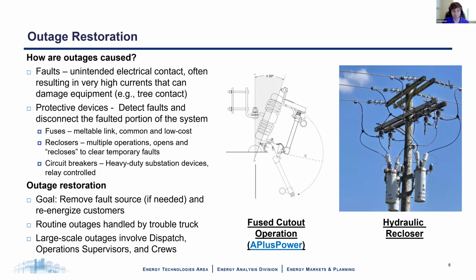We also have reclosers, which have multiple operation cycles. It can detect a fault, open itself, and then it recloses back in to see if that fault is still present. And if it is, it'll open again. If the fault is gone, however, it'll remain energized. So if you had a temporary fault that's not there anymore, if the tree branch fell off after it got toasted, then it'll keep everything energized. And then the third category, circuit breakers. These are relatively heavy duty substation devices that are relay controlled. They can also do reclosing, but are just a little bit beefier and not really suited for mounting on top of a pole.